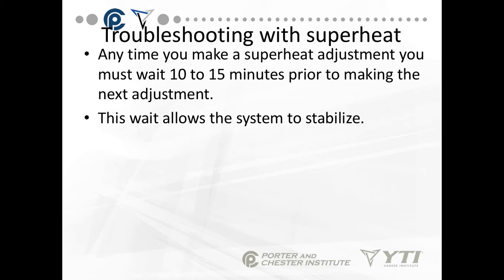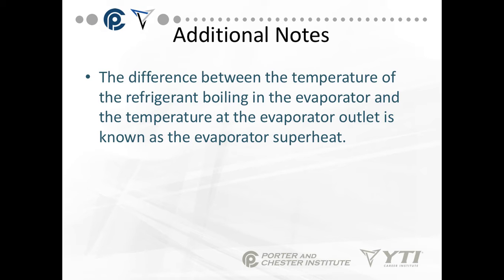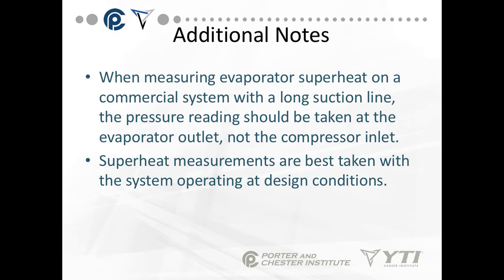The difference between the temperature of refrigerant boiling in the evaporator and the temperature at the evaporator outlet is known as evaporator superheat. When measuring evaporator superheat on a commercial system with a long suction line, pressure readings should ideally be taken at the evaporator outlet, not the compressor inlet. In practice you're usually not able to do that, which is why you add the 2 psi adjustment. Superheat measurements are best taken with the system operating at design conditions — the box cold, the evaporator cold, out of defrost, and stable.